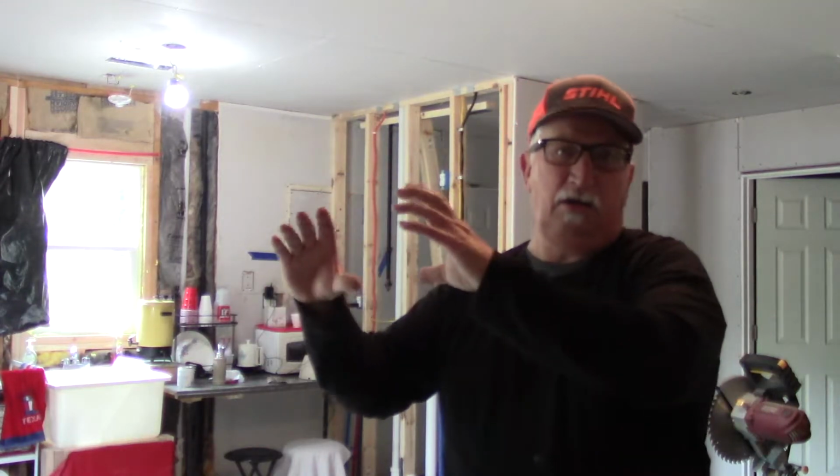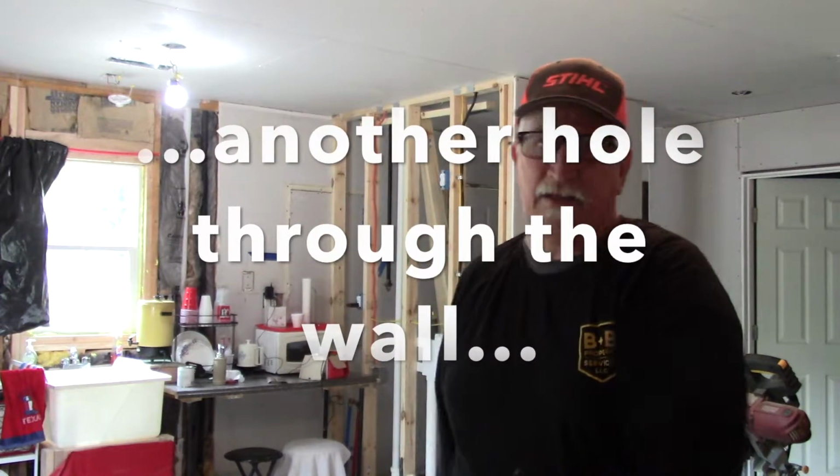One of them was that the exhaust fan in the bathroom is more than 5 feet from the exterior wall, so it has to have insulated ductwork on it for that 7 feet to go from the fan to the outside wall. And we had it hooked up on an existing big vent. It had a collar and everything on it, but the inspector didn't like that. Said no, it has to have its own completely separate vent. So we fixed all of that.